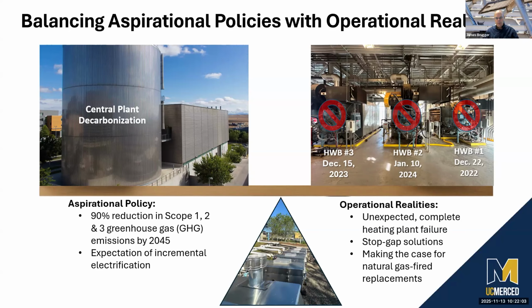One of the stopgaps we had to do as our boilers failed—after the first one failed, we started renting boilers. We currently have 9 rental boilers firing our heating plant at a cost of about $35,000 a month while we're trying to get this replacement going. And that real estate is needed for heat pump technologies and other things we're going to implement as part of our decarb strategy down the road.